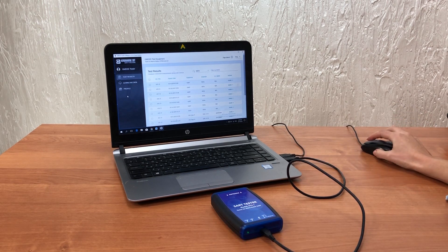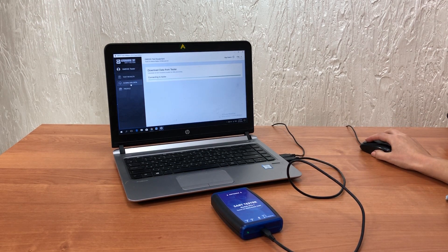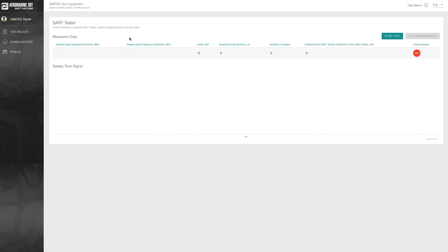Then go to the download data menu. For the first connection on Windows you will need to press the button to connect the COM port manually. This is the SART tester operation window. Here is the start test button and the check pass status. When the SART passes the test successfully the check status shows OK. So press start test.